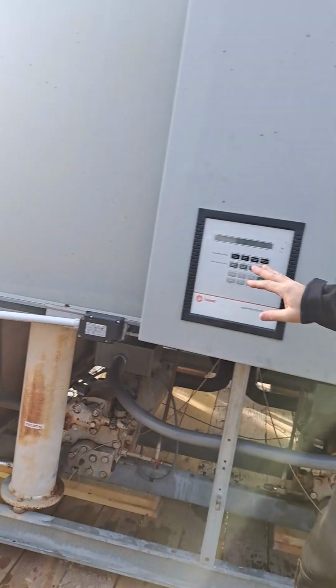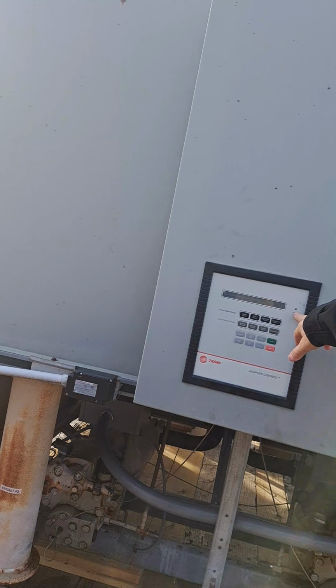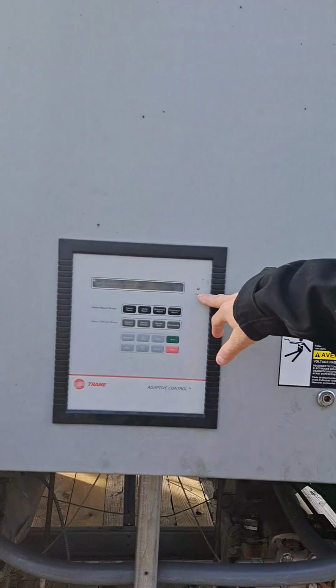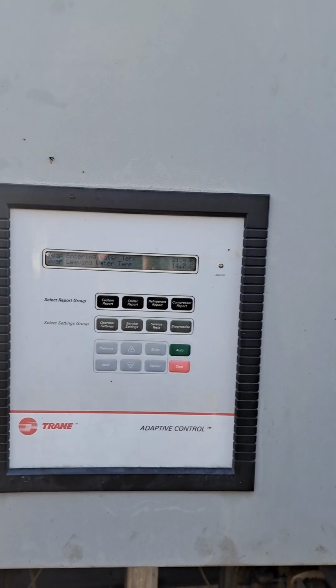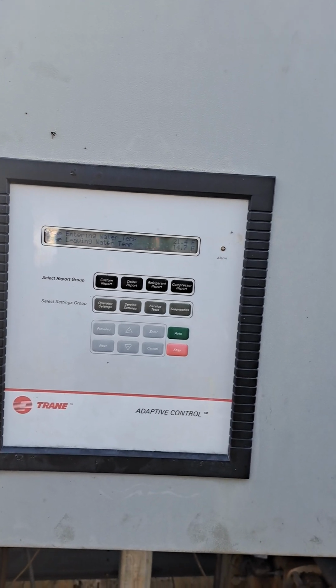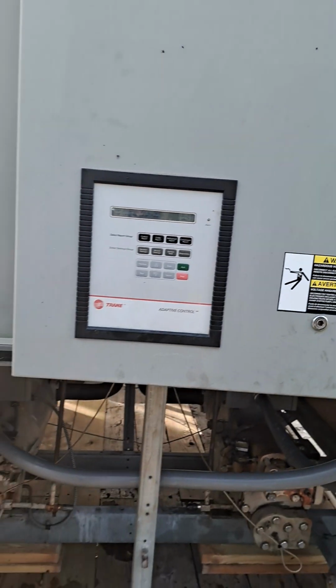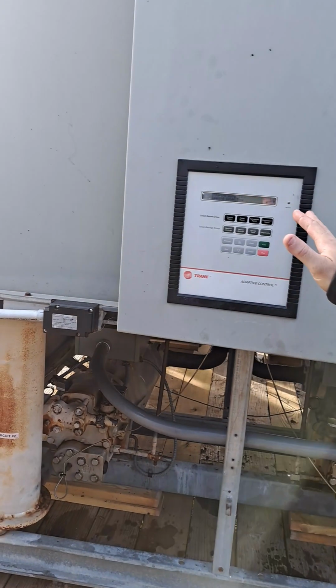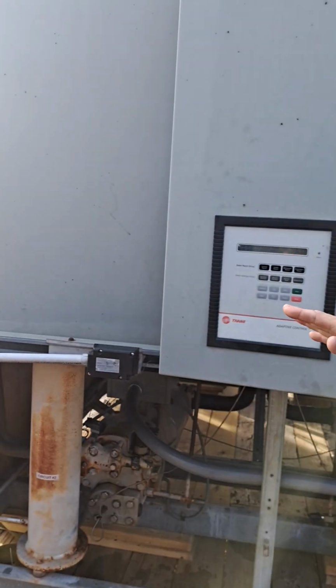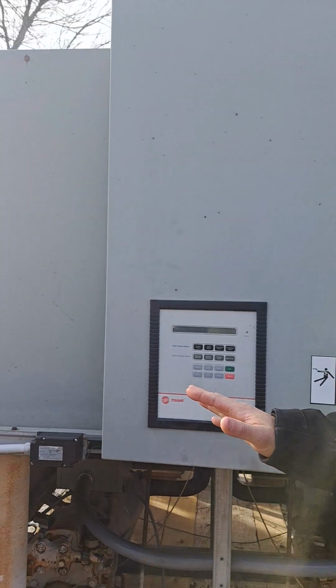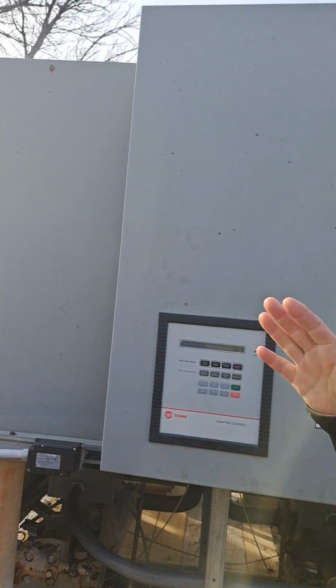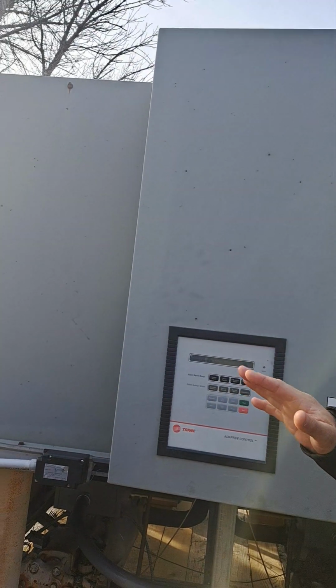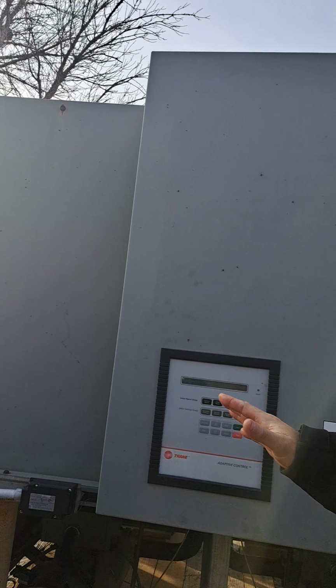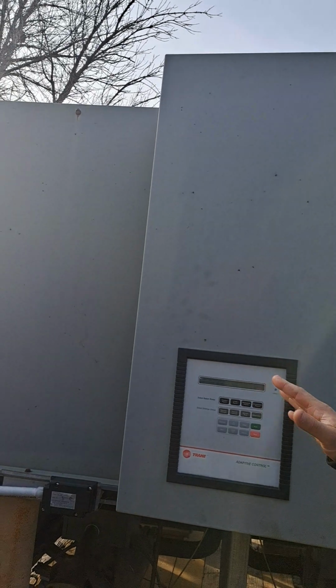If you have any problems, this alarm light's going to be flashing on it. Okay. So we did get a low refrigerant pressure alarm earlier. I had to change all the settings on this. This machine was not designed for these temperatures. This machine was designed for comfort cooling, which is 40-degree water. So I had to change all of the safeties and the programming on it to make it run down to 15 degrees. So you may see a few alarms on here occasionally, low refrigerant or whatever.